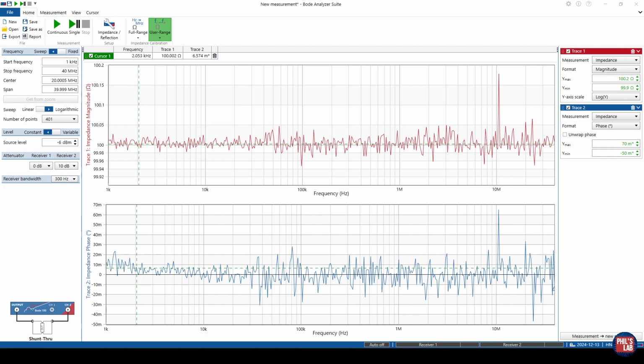I won't be recalibrating for the sake of time. I've just done a 0 volt DC bias calibration, and here's the result after measuring a 100 ohm resistor. You can see we're getting nominally 100 ohms. There are some minor excursions, and we're getting about 0 degrees of phase after the open short load calibration, again with the DC blocks as well as the common mode choke.